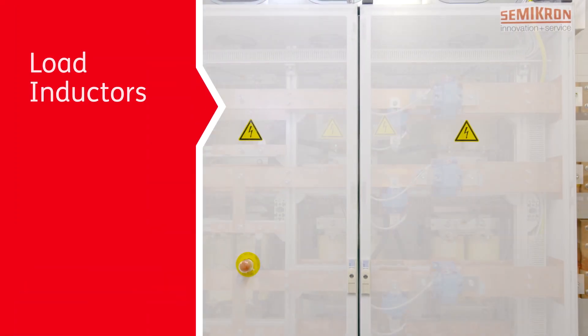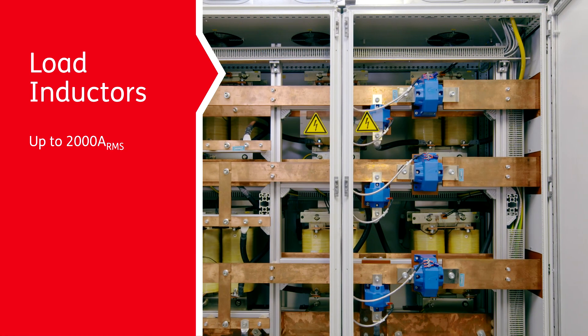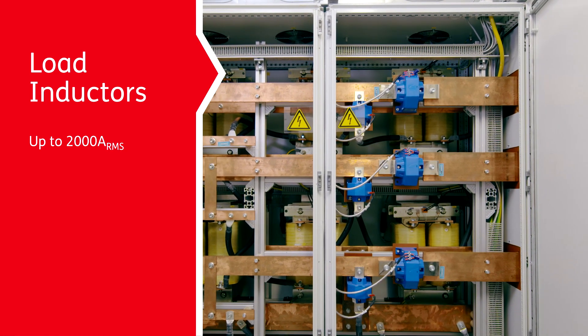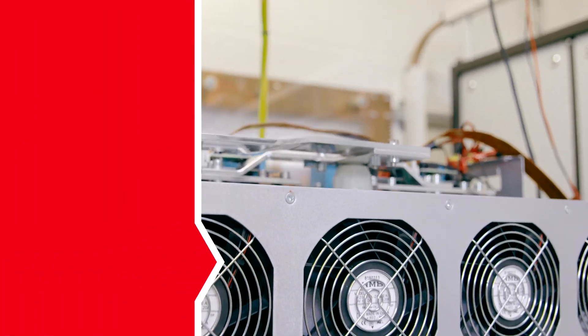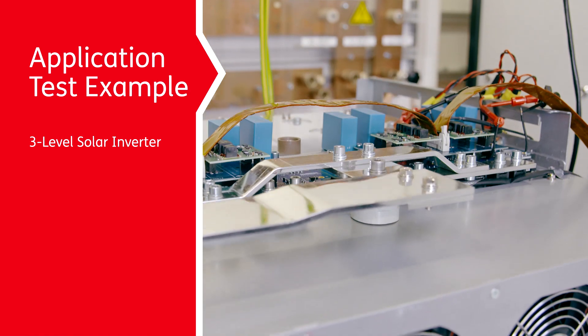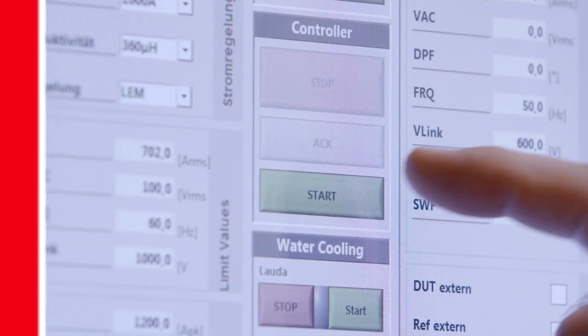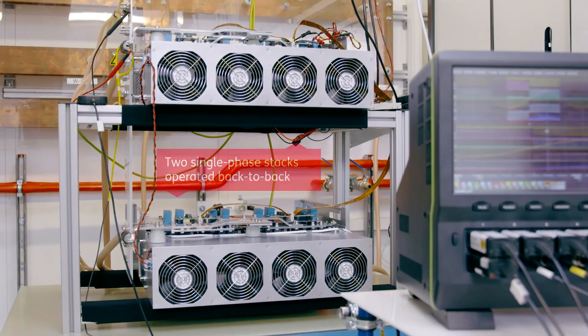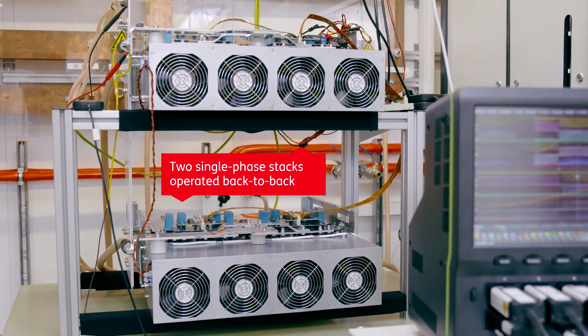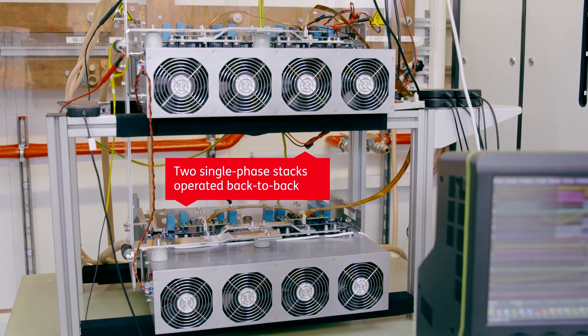The load inductors can handle up to 2000 amps of RMS current. Here, you can see one of our tests in action. The test inverter shown here is a three-level solar stack comprising four SEMIX-5 modules in parallel. The test setup is two single-phase stacks operating back-to-back.